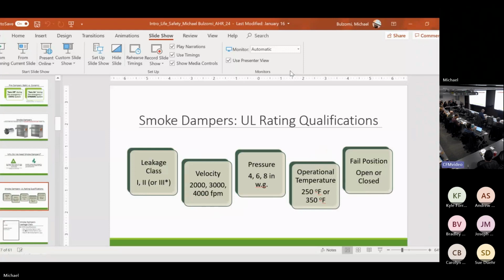Here are our rating qualifications for smoke dampers. Again, call my car salesman. Leakage class, right? We're trying to prevent the movement of smoke. Leakage is the most important. There are 2 options, class 1 or class 2. The International Building Code for the United States requires a minimum class 2 leakage rating on all smoke and combination fire smoke dampers. I do show class 3 with an asterisk. Canada allows class 3. Other countries that don't follow the International Building Code allow class 3. So some manufacturers still build a class 3. We do not at Greenheck, but some do.